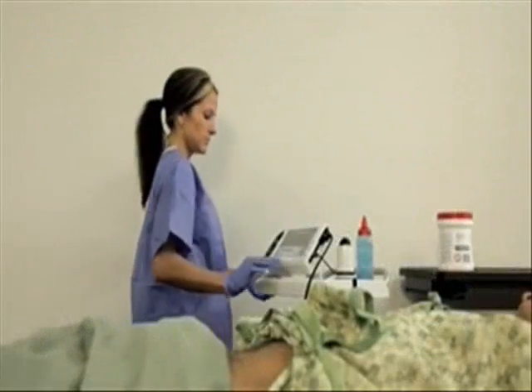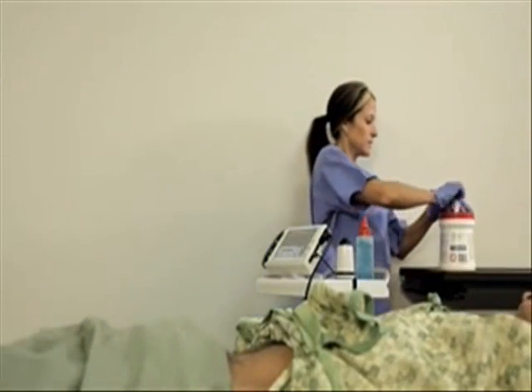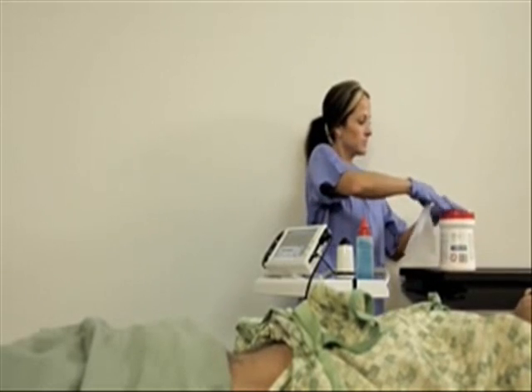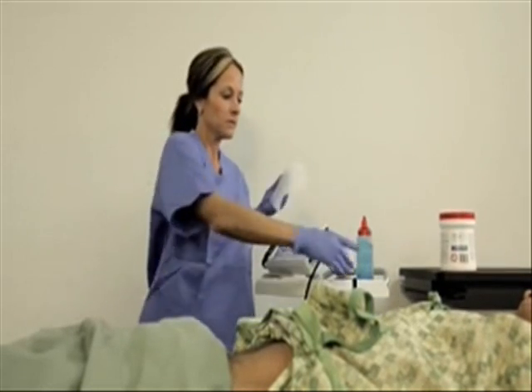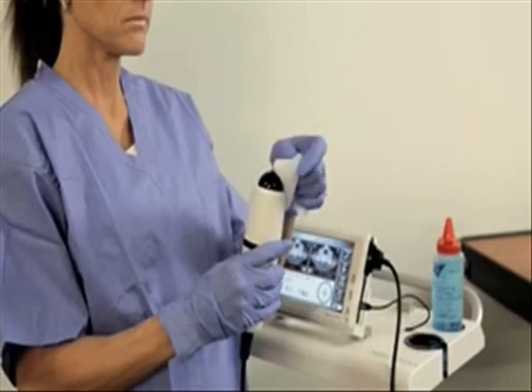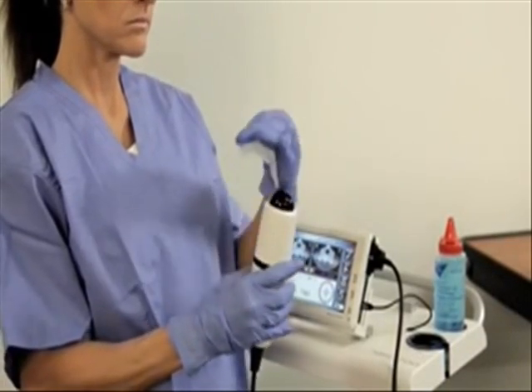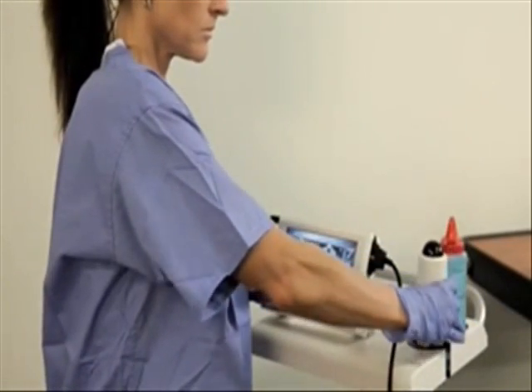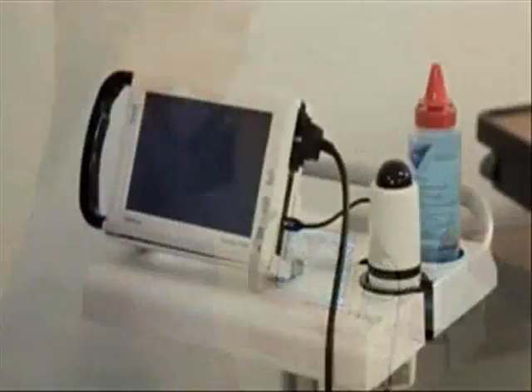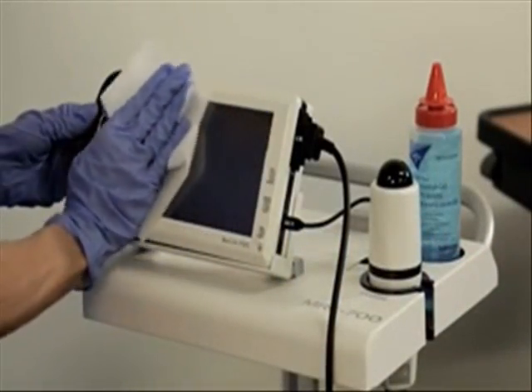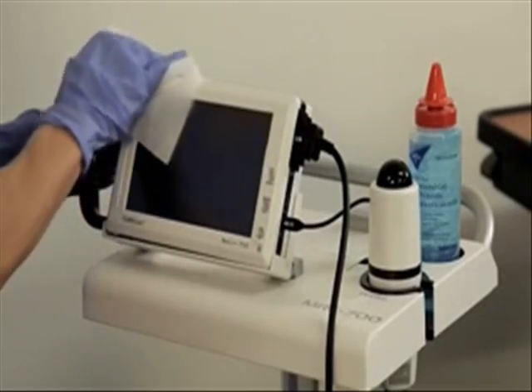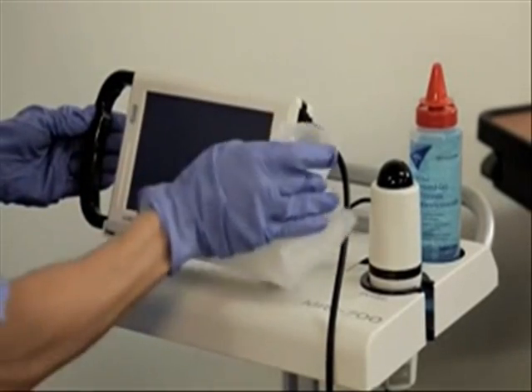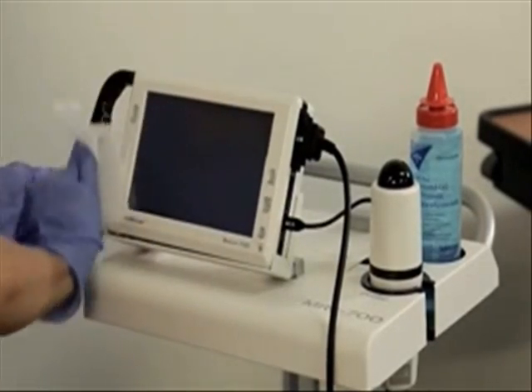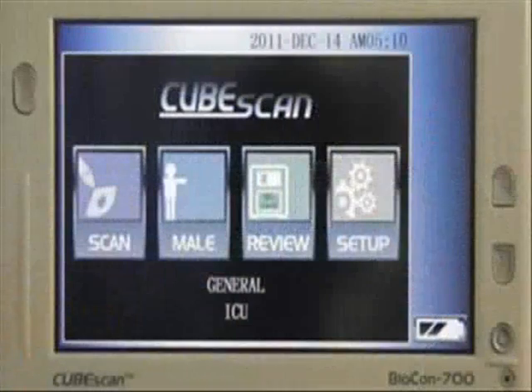To disinfect the probe after a scan, wipe off any residual gel from the probe. Dampen a soft cloth with disinfection solution or wipe, and then wipe the probe with the cloth. Air dry or towel dry with a soft, clean cloth. To clean the main unit, wipe it 1 to 2 times using a soft cloth dampened with isopropyl alcohol or another appropriate hospital cleaning solution.